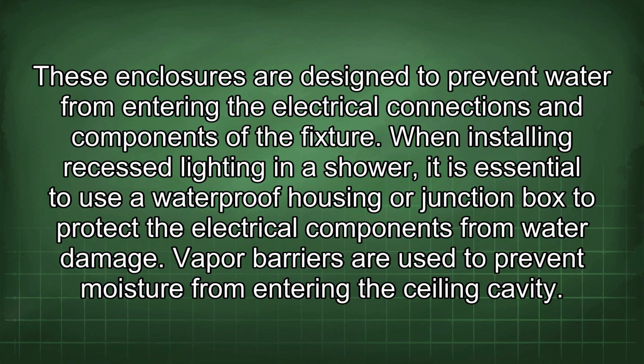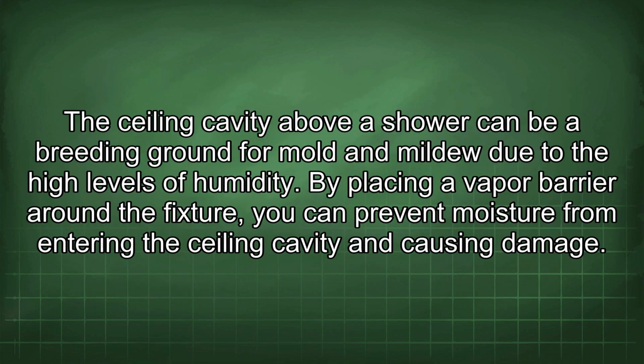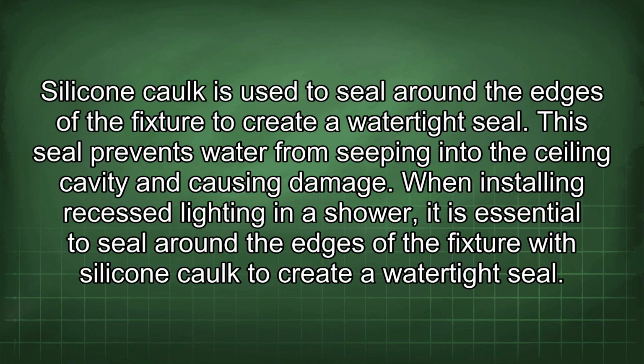Vapor barriers are used to prevent moisture from entering the ceiling cavity. The ceiling cavity above a shower can be a breeding ground for mold and mildew due to the high levels of humidity. By placing a vapor barrier around the fixture, you can prevent moisture from entering the ceiling cavity and causing damage. Silicone caulk is used to seal around the edges of the fixture to create a watertight seal. This seal prevents water from seeping into the ceiling cavity and causing damage. When installing recessed lighting in a shower, it is essential to seal around the edges of the fixture with silicone caulk to create a watertight seal.